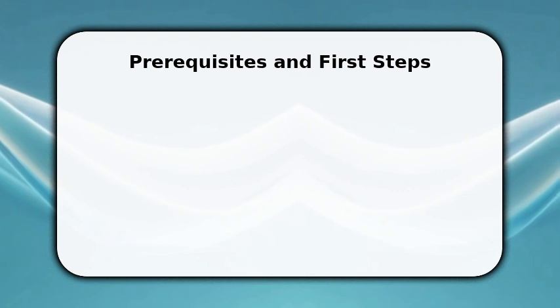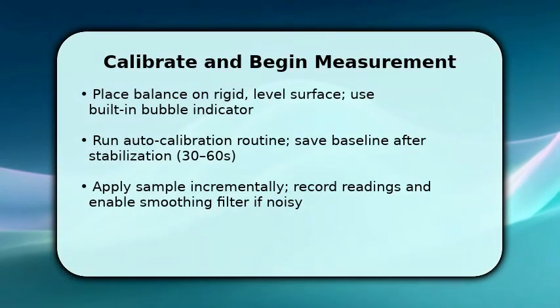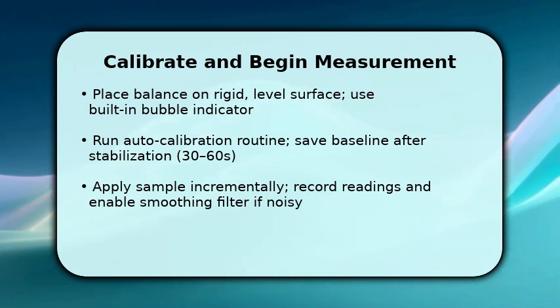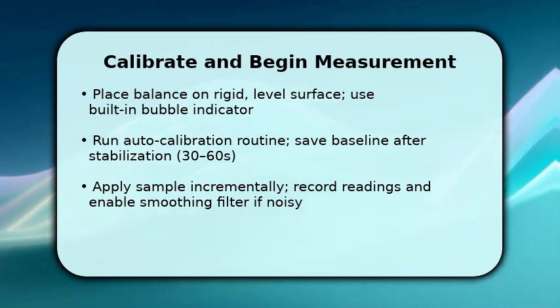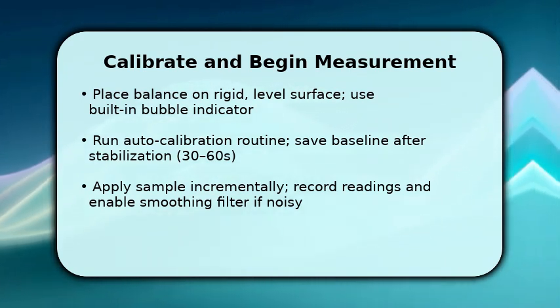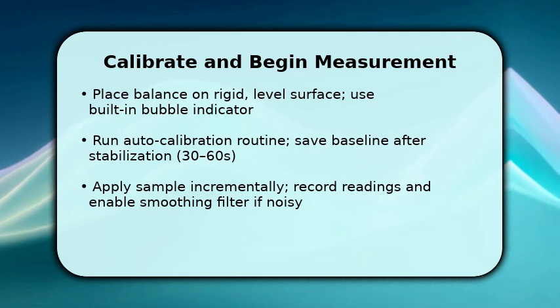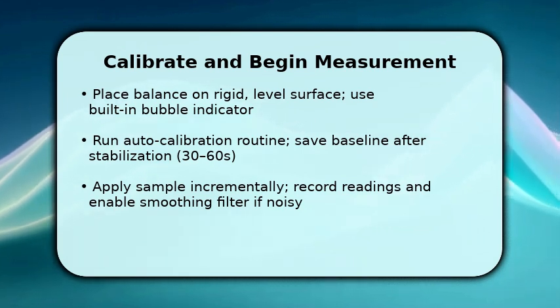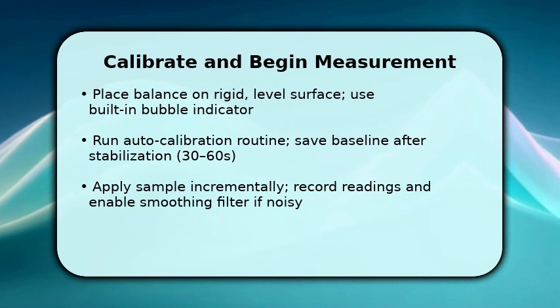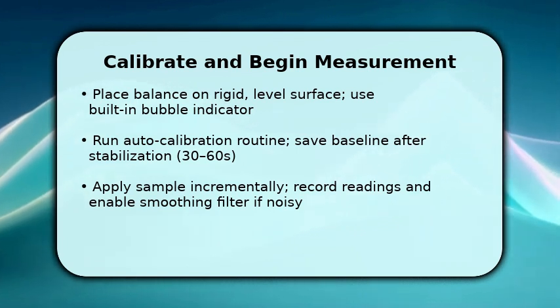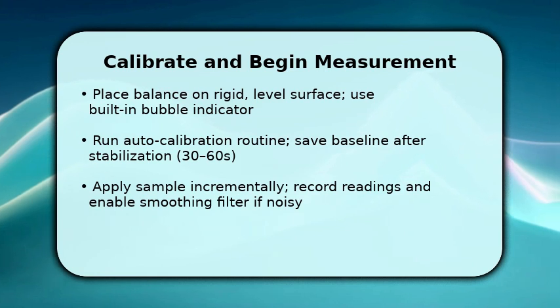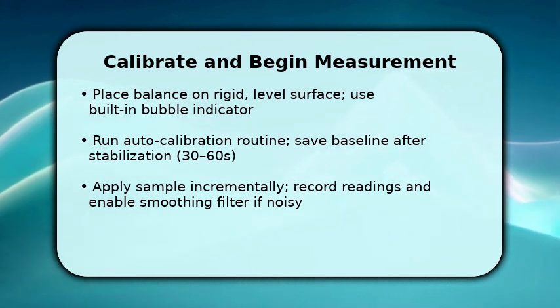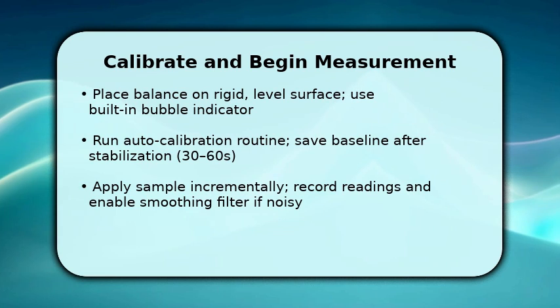Now you calibrate and start measuring. Place the balance on a rigid, level surface and use the built-in bubble indicator so measurements stay accurate. Uneven placement introduces systematic error. Then run the auto-calibration routine and wait 30 to 60 seconds for stabilization before saving the baseline, because thermal drift settles in that window. Once baseline is set, apply samples incrementally and watch live readouts.